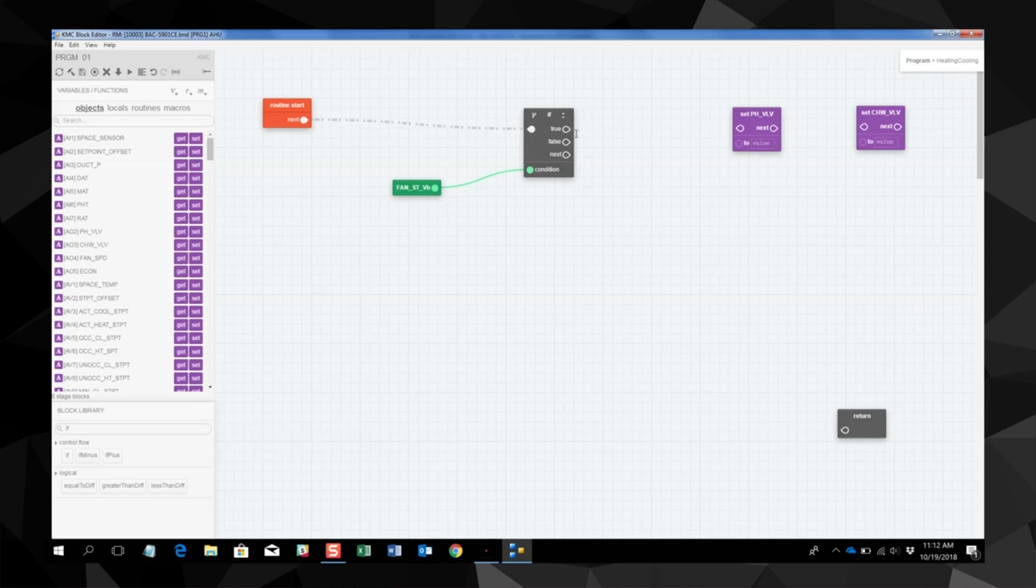We'll take the true value so when the fan status is true, we're going to allow both the hot water valve and the chill water valve to work. The program is looking for a value and when it is found, the value is then highlighted.